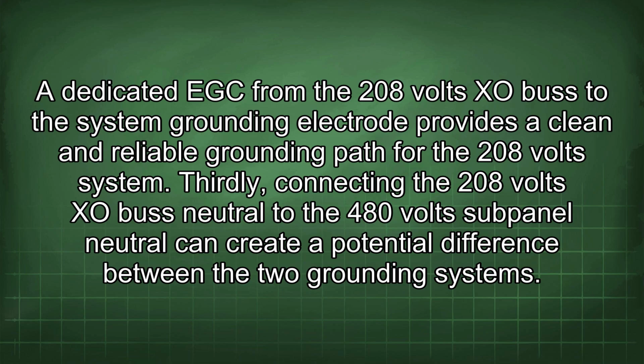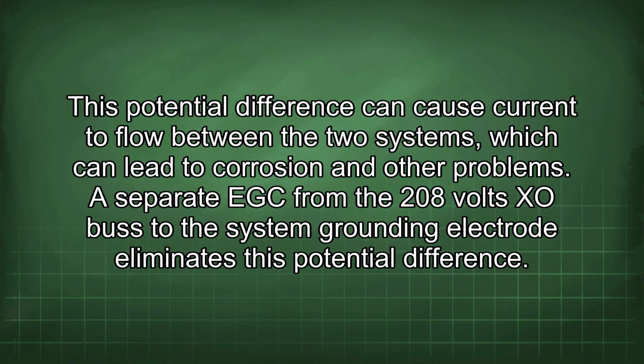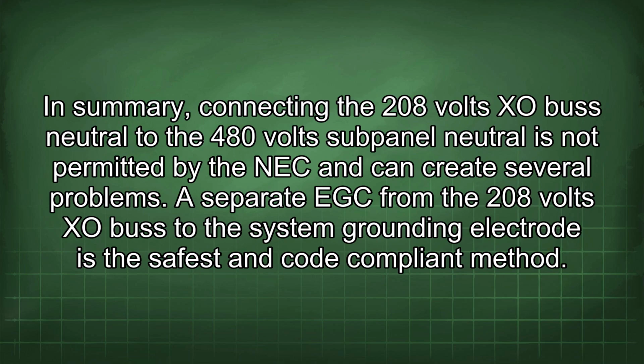Thirdly, connecting the 208 volts XO bus neutral to the 480 volts subpanel neutral can create a potential difference between the two grounding systems. This potential difference can cause current to flow between the two systems, which can lead to corrosion and other problems. A separate EGC from the 208 volts XO bus to the system grounding electrode eliminates this potential difference. In summary, connecting the 208 volts XO bus neutral to the 480 volts subpanel neutral is not permitted by the NEC and can create several problems. A separate EGC from the 208 volts XO bus to the system grounding electrode is the safest and code-compliant method.